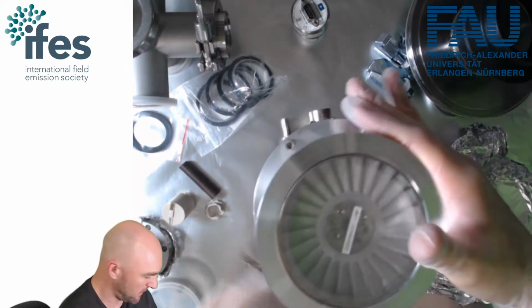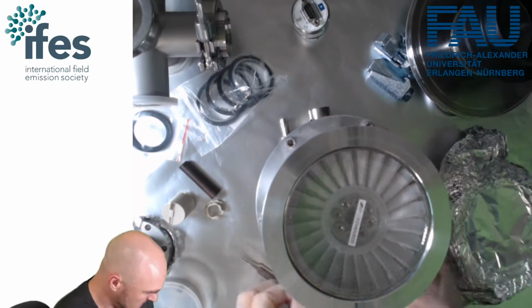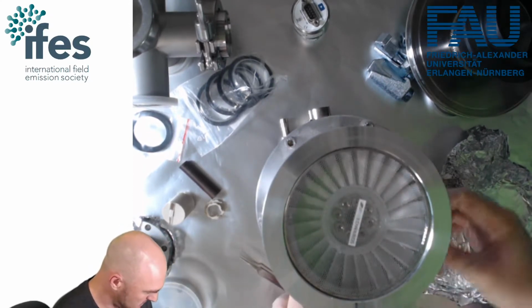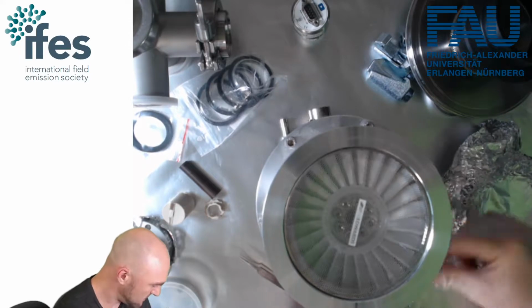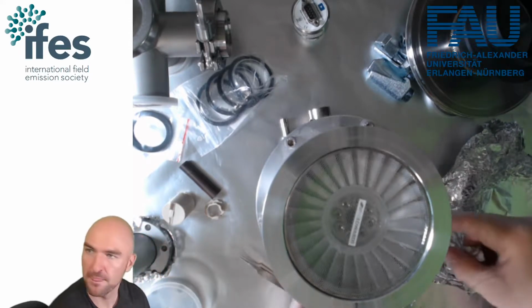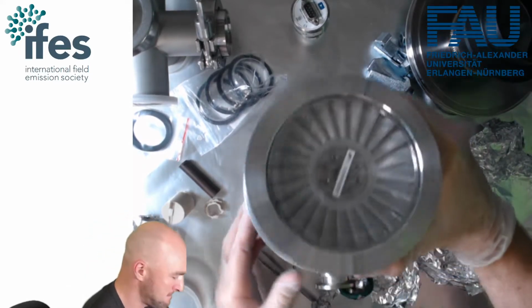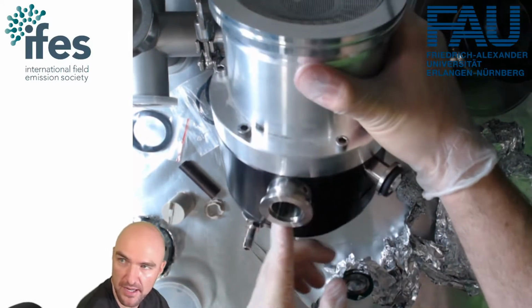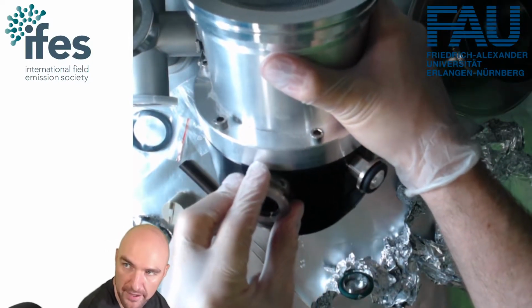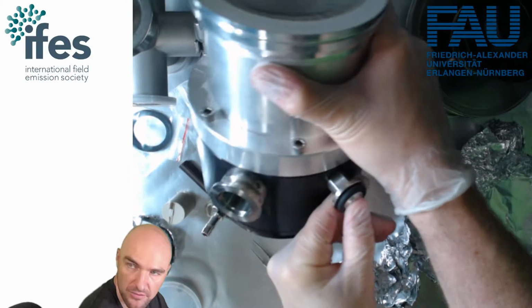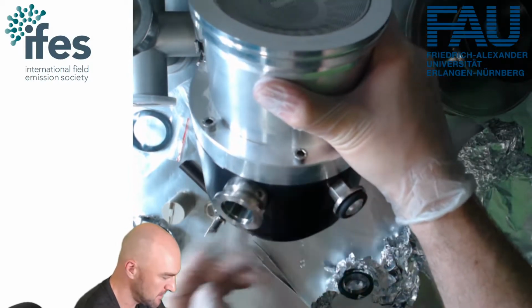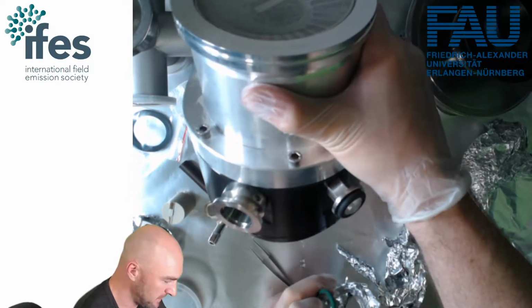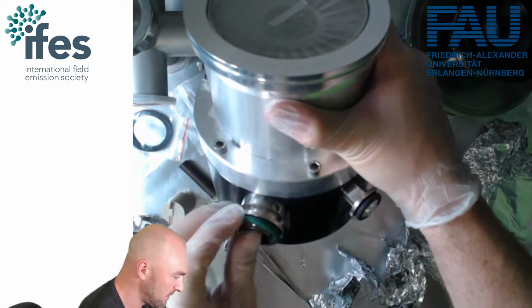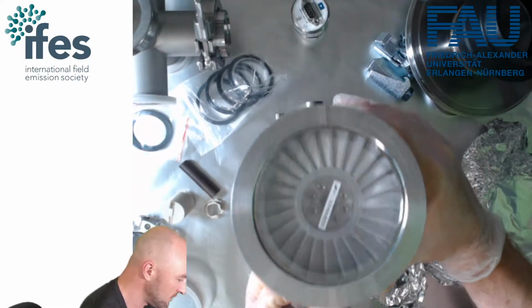This pump, then you can see here, you've got an outlet, and on the side, you've got an outlet. So this is where you would put the backing pump, and here you've got a second thing that looks like an outlet but isn't actually one. What that thing is, is a venting valve.